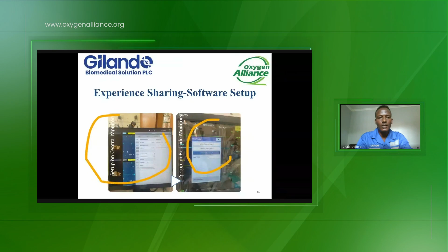Second, we set up the software, first at the site of the central monitoring. This is the central monitoring setup, where we set the IP address, gateway, and ports. And this is where we set the network setup from the patient side monitors. On the patient side monitors, we set the network setup, the selection of the central monitoring system, and ports and IP address. As you can see here on the patient side, these are what we can set in the network setup and selection of a central monitoring system.